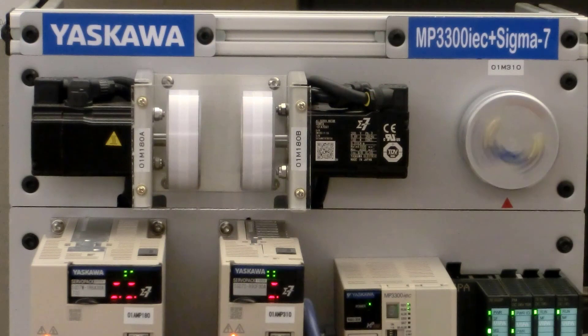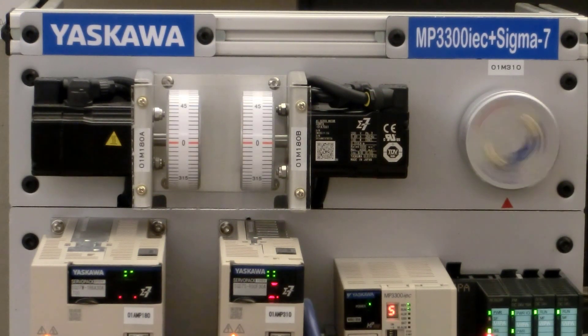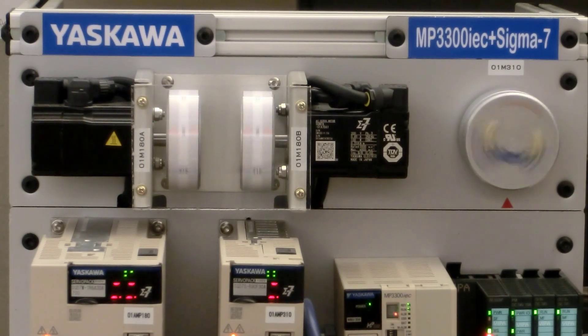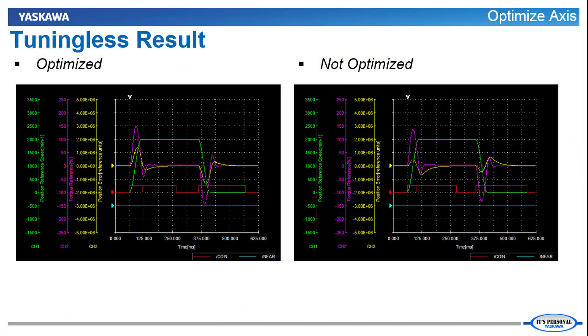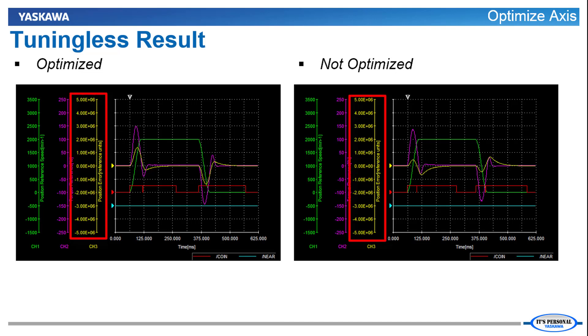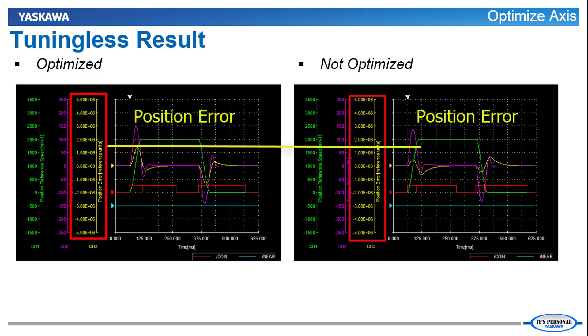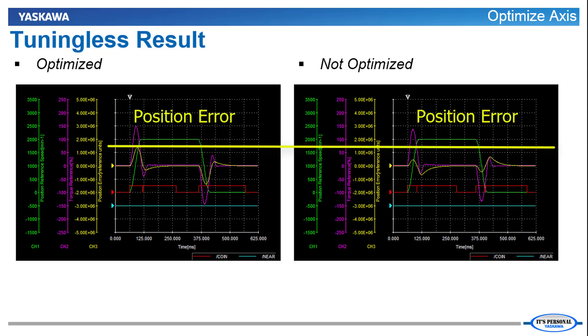The MP3300 IEC is programmed to command the same cam profile on both axes. I'll show the result of the tuning process using traces taken from our software Sigma-Win+. By default, the servos are in the adaptive tuningless mode, and you can see the two traces are about the same. The position error of the optimized axis is actually significantly higher than the original not-optimized axis.